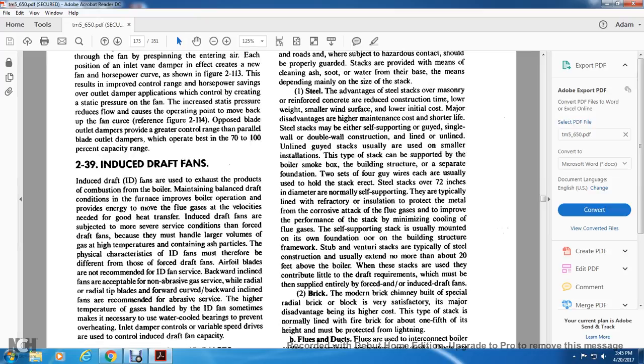Alright, one, steel. The advantages of steel stacks over masonry or reinforced concrete are reduced construction time, lower weight, smaller wind surface, and lower initial cost. The major disadvantages are higher maintenance costs and shorter life. Steel stacks may either be self-supporting or guyed, and single wall or double wall construction, lined or unlined. Guyed stacks are usually used in smaller installations.